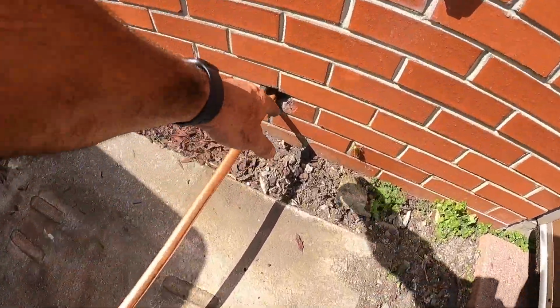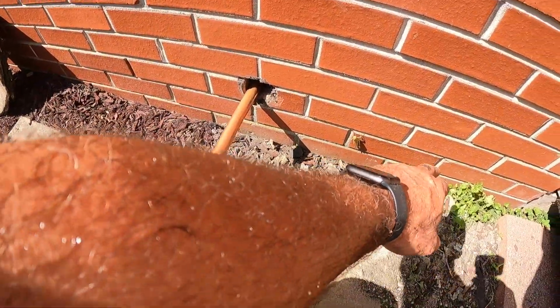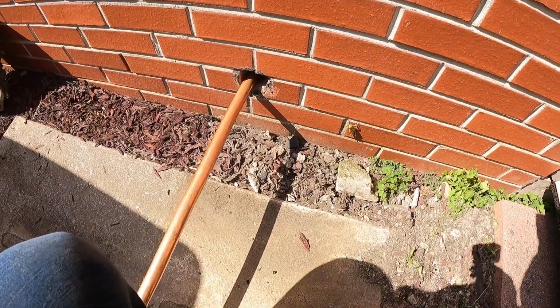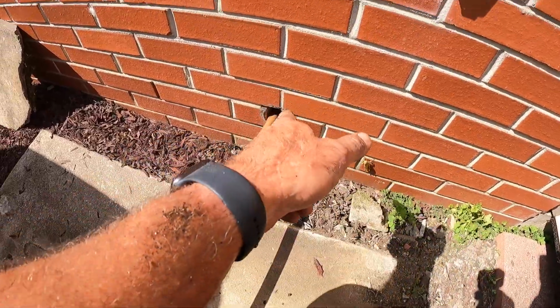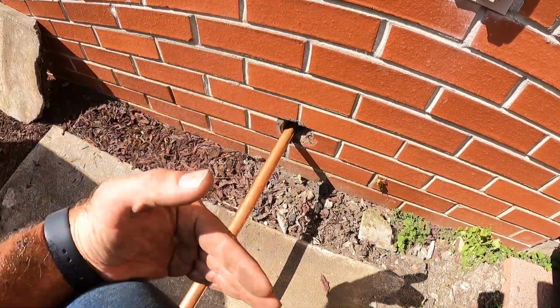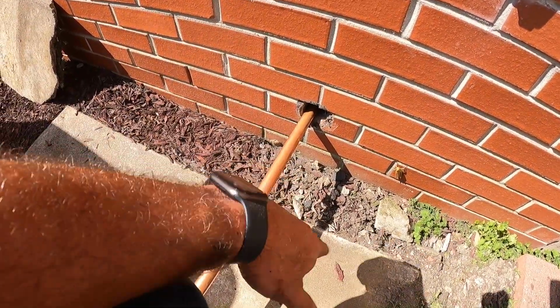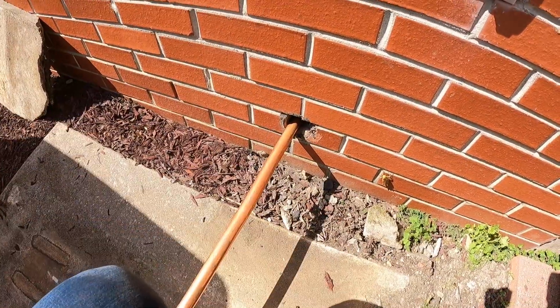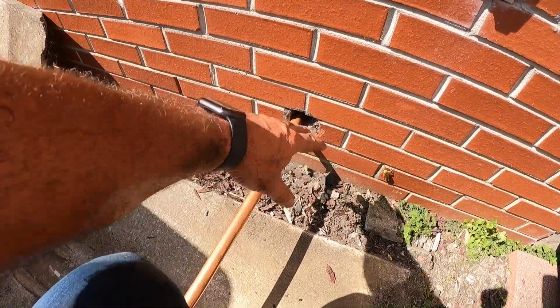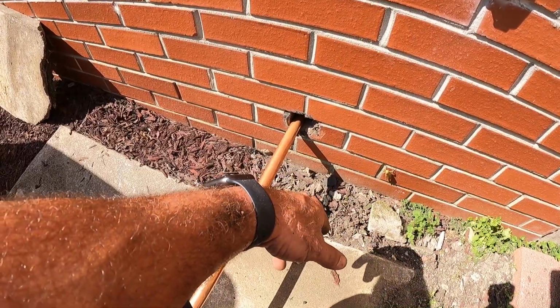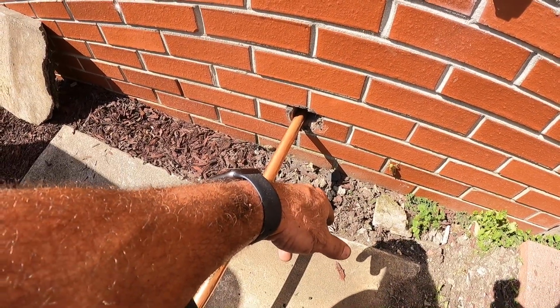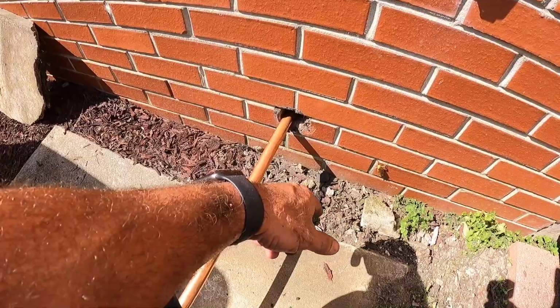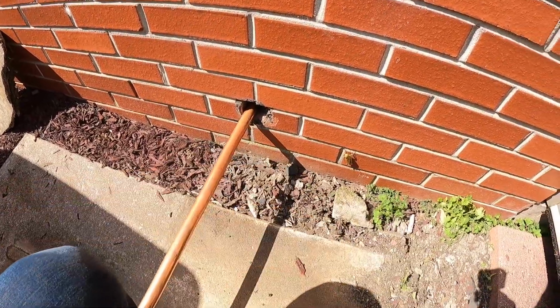I'm going to have to go 90 over and 90 back. The easiest way to do that is mark it, pull it out a little bit, put my bender in here, bend it, and push it back again. Otherwise you end up putting that reverse bending attachment on, and it's just a mess trying to get it to work without kinking the copper up. So I'd prefer to just use the normal bender for this.